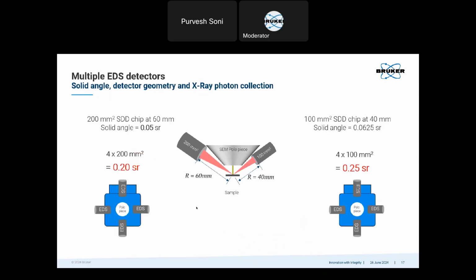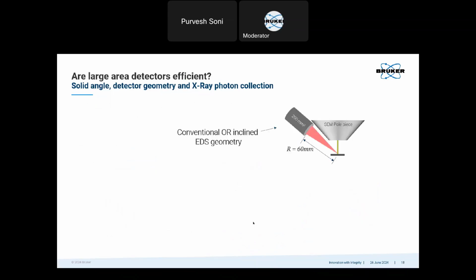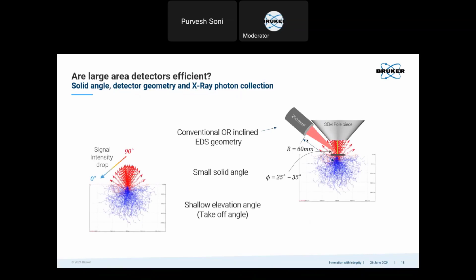What you could do, if you have free ports, is have 2 or 4 detectors to improve the solid angle, but still it's quite low. The problem with conventional detector geometry is that the solid angle is very small, and also the elevation angle is very shallow. So we are collecting X-rays where the signal is very diffused and heavily absorbed. The signal intensity drops as we go from 90 degrees to 0 degrees, and we are collecting at around 25 to 35 degrees elevation angle, so the signal intensity is quite weak at these angles.